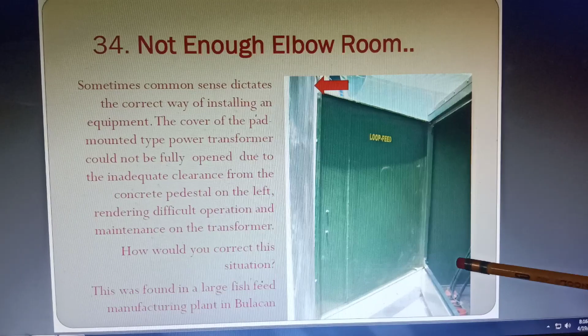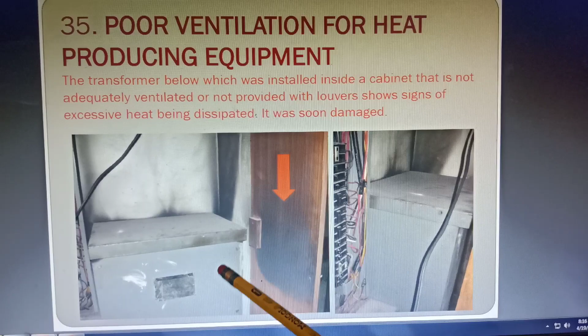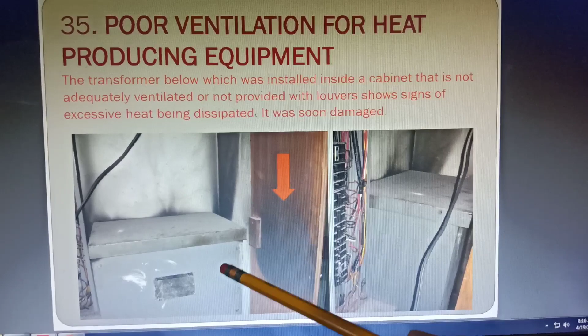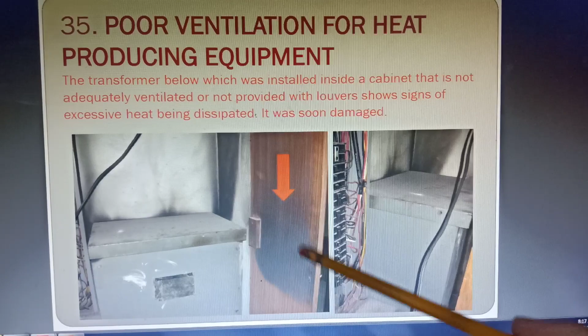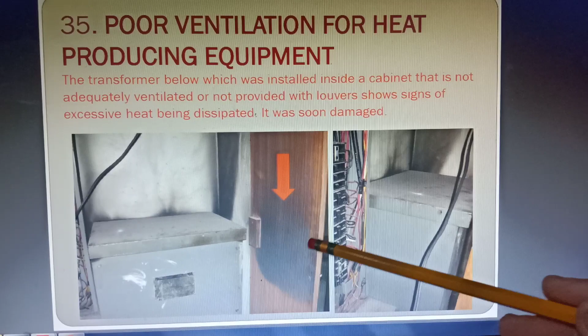Okay, here we would see a step down transformer in an office building where you would see dark colors here or shades, meaning to say the transformer might have been overloaded several times, so it is experiencing overheating, so that this would be the cause, no? So the idea is this door panel, the cabinet panel, would have been provided with louvers, no? Pahingahan niya, no? Louvers para sana ma-ventilate itong transformer inside the room.